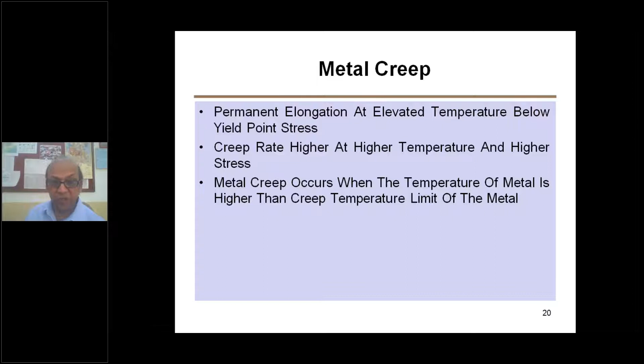Now see the data. The creep temperature for steel is 270 degrees centigrade. It means 270 degrees centigrade. After that, the permanent deformation in the steel will occur. Okay, so we have to take care when steel temperature becomes more than 270 degrees. Copper, this temperature is 135 degrees centigrade. So up to 135 degrees centigrade, no serious problem. After that, problem starts. In aluminium, this temperature is only 7 degrees centigrade. It means even at room temperature, this is going to cause the problem. There is going to be permanent deformation.